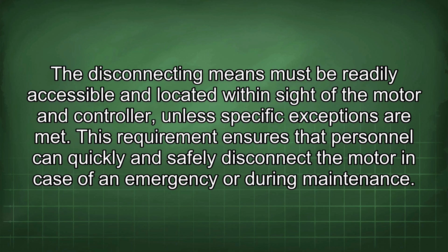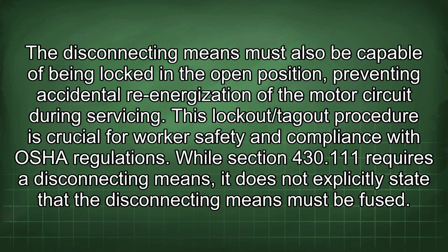during maintenance. The disconnecting means must also be capable of being locked in the open position, preventing accidental re-energization of the motor circuit during servicing. This lockout/tagout procedure is crucial for worker safety and compliance with OSHA regulations.